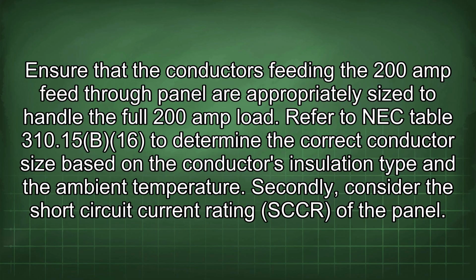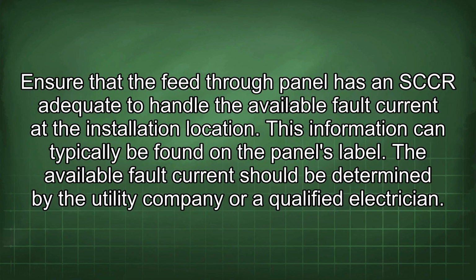Secondly, consider the short circuit current rating (SCCR) of the panel. Ensure that the feed-through panel has an SCCR adequate to handle the available fault current at the installation location. This information can typically be found on the panel's label. The available fault current should be determined by the utility company or a qualified electrician.